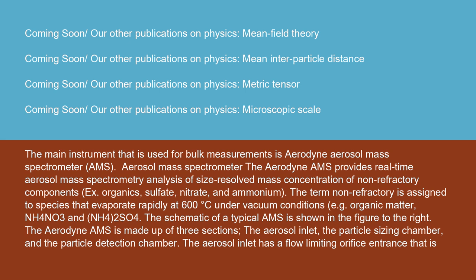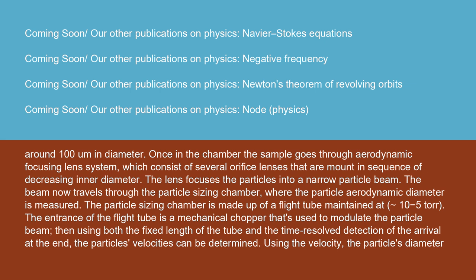The aerosol inlet has a flow-limiting orifice entrance around 100 µm in diameter. Once in the chamber, the sample goes through an aerodynamic focusing lens system, which consists of several orifice lenses mounted in sequence of decreasing inner diameter that focuses the particles into a narrow particle beam. The beam then travels through the particle sizing chamber, where the particle aerodynamic diameter is measured. The particle sizing chamber is made up of a flight tube maintained at 10⁻⁵ Torr. The entrance of the flight tube has a mechanical chopper used to modulate the particle beam, and using the fixed length of the tube and the time-resolved detection of arrival at the end, the particle's velocity and diameter are obtained.